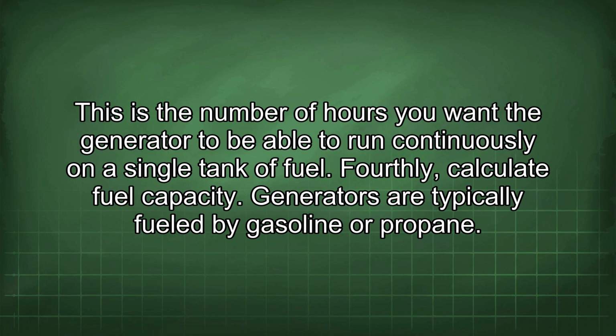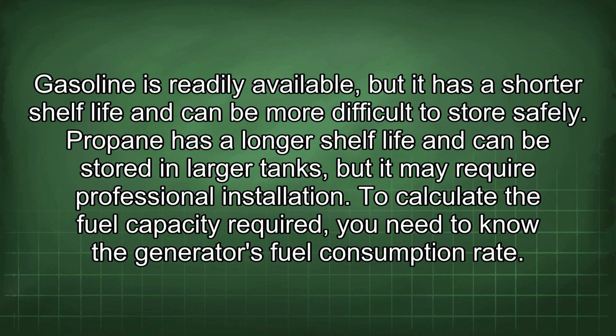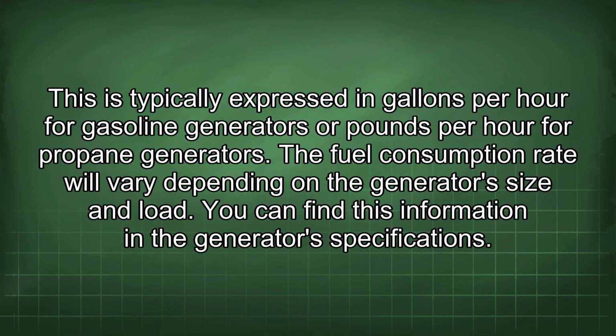Fourthly, calculate fuel capacity. Generators are typically fueled by gasoline or propane. Gasoline is readily available, but it has a shorter shelf life and can be more difficult to store safely. Propane has a longer shelf life and can be stored in larger tanks, but it may require professional installation. To calculate the fuel capacity required, you need to know the generator's fuel consumption rate. This is typically expressed in gallons per hour for gasoline generators or pounds per hour for propane generators. The fuel consumption rate will vary depending on the generator's size and load. You can find this information in the generator's specifications.